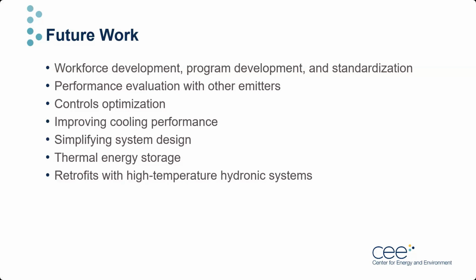Another key topic would be improving cooling performance, where there is a balance to be struck between making heating season adjustments that might sacrifice cooling efficiency, and also the effect of switching between cooling and heating for domestic hot water supply. While it was not possible with these systems, potentially dumping extracted heat from cooling mode into the DHW tank could improve how these two modes interact with each other.